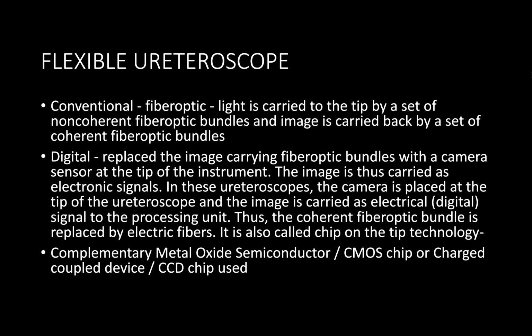A flexible ureteroscope has an eyepiece, a light post, and a lever which allows for deflection of the distal tip, up to 150 degrees on either side. In terms of the digital flexible ureteroscopes, they do not use fiber optic bundles for image transmission. They instead work on the principle of a photon striking a charge coupled device, which is found at the tip of the scope, and this provides a superior image quality. Furthermore, flexible scopes have one working channel, and this is normally 3.6 French.